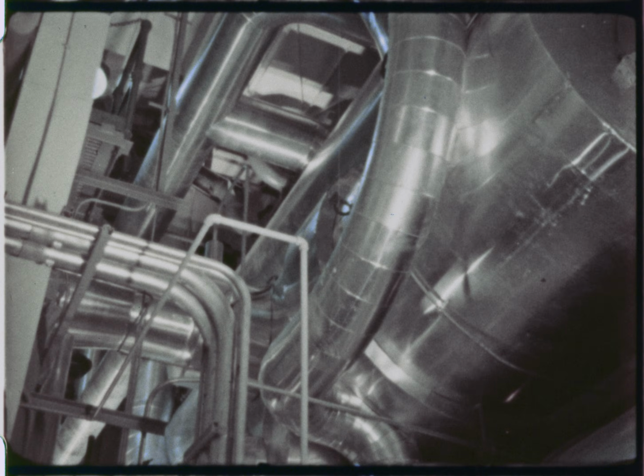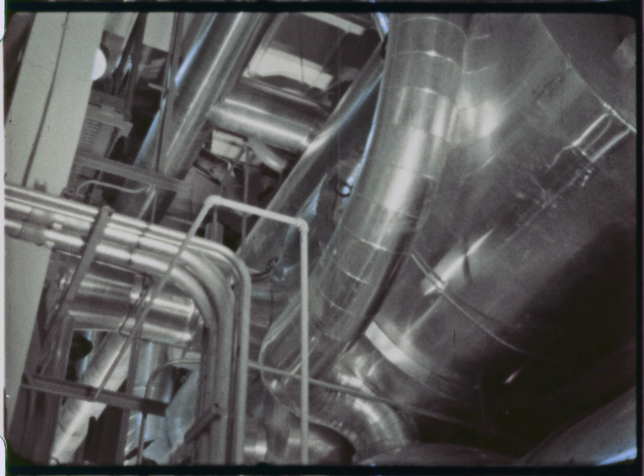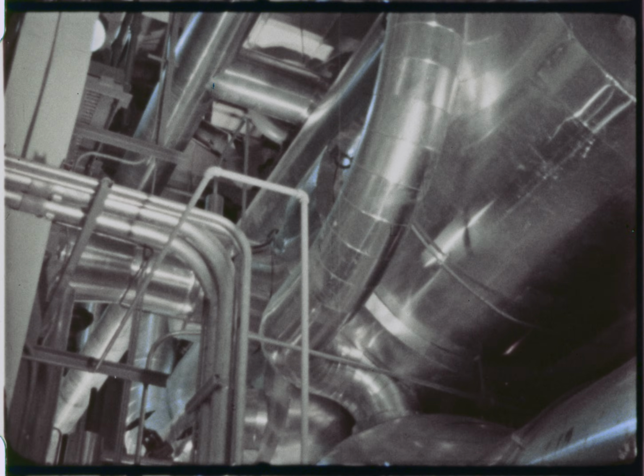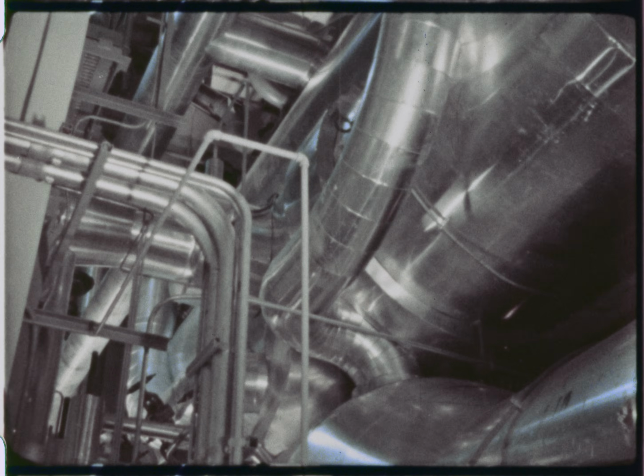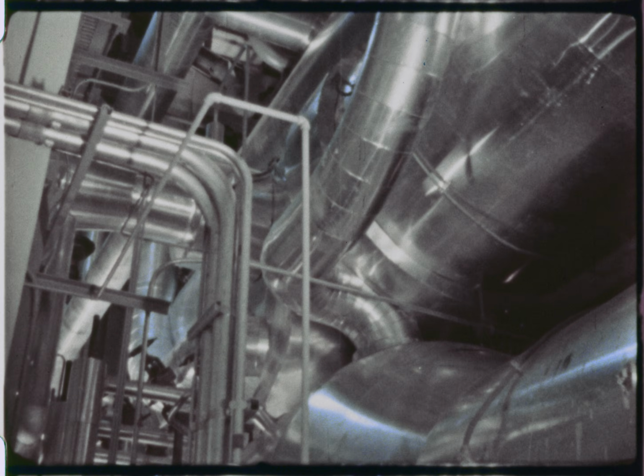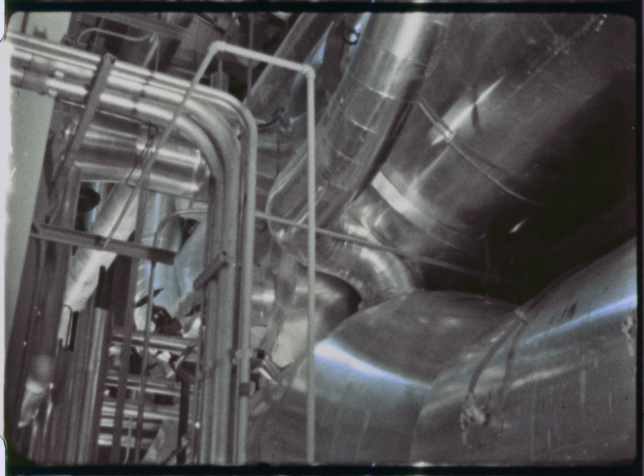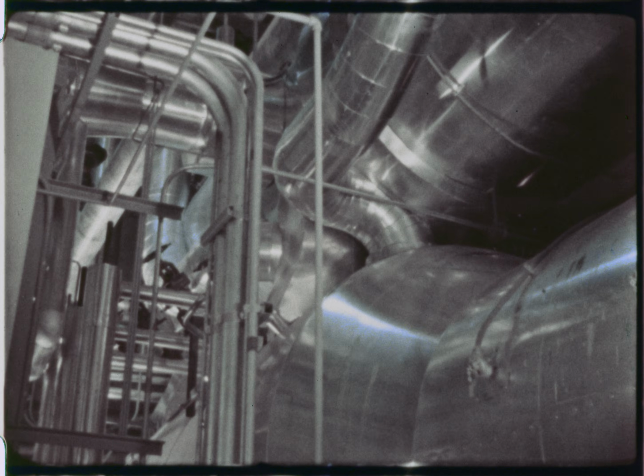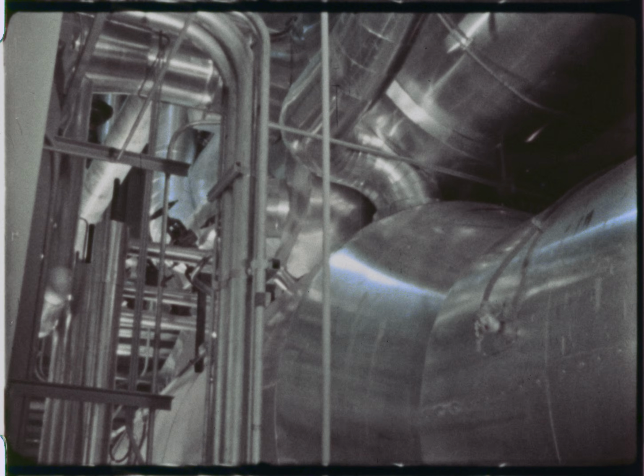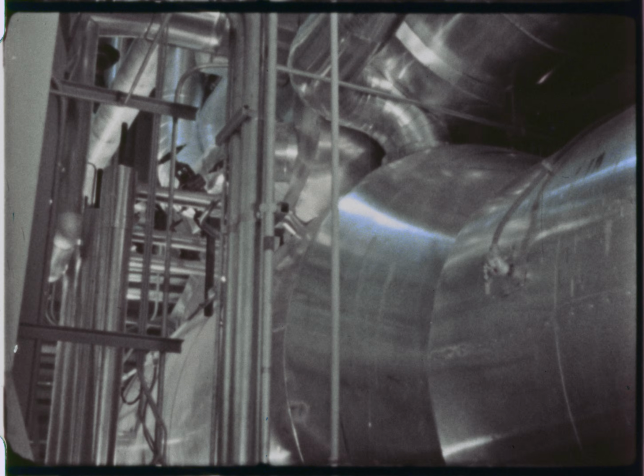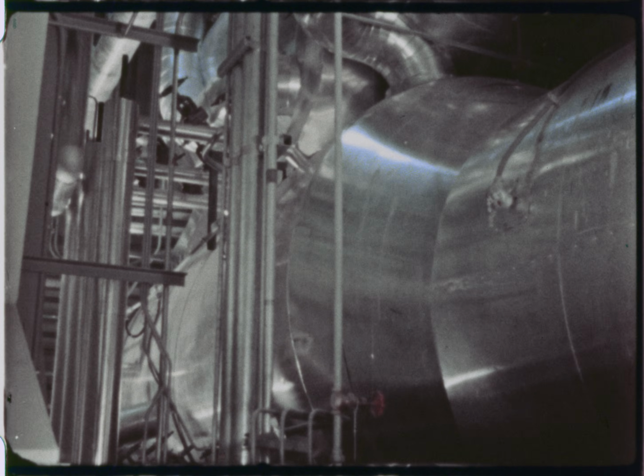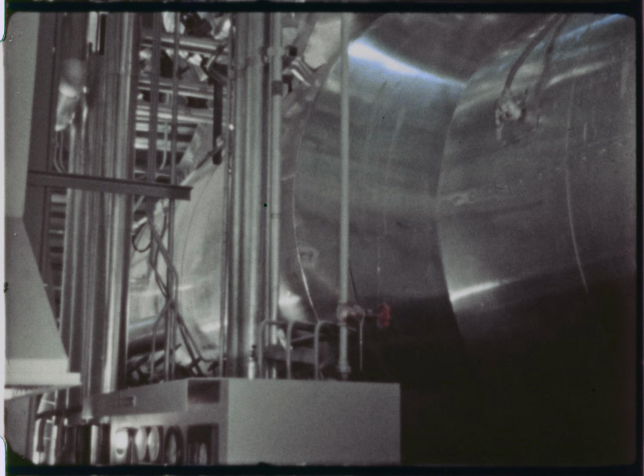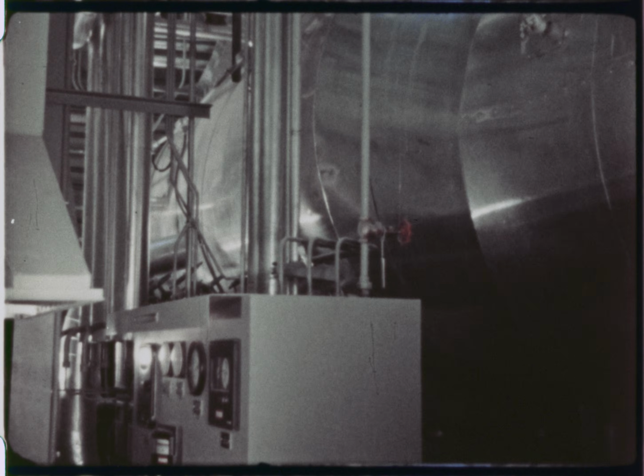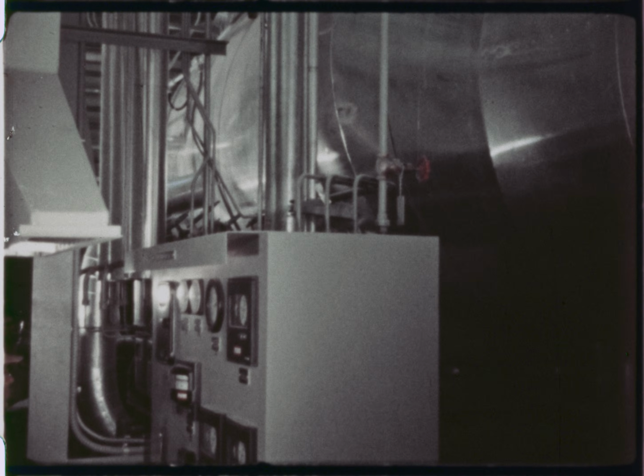Each steam generator consists of an evaporator, moisture eliminator, and superheater. Construction is of the shell and tube type, using double-walled bayonet tubes to prevent leakage between sodium and water systems. The bayonet tubes utilize helium between the 2 walls as a monitor for leaks. The evaporator is a kettle-type design, with the water carried in the shell. The moisture eliminator delivers dry steam to the superheater.